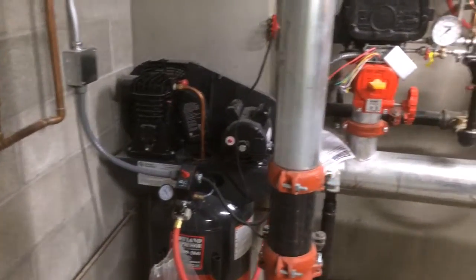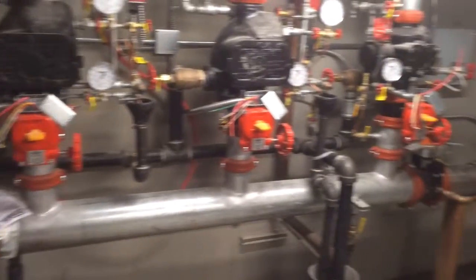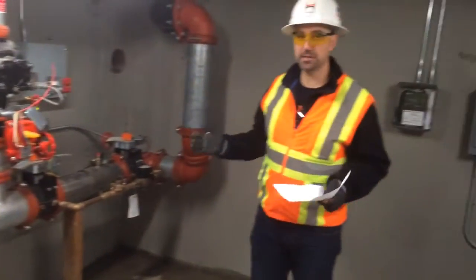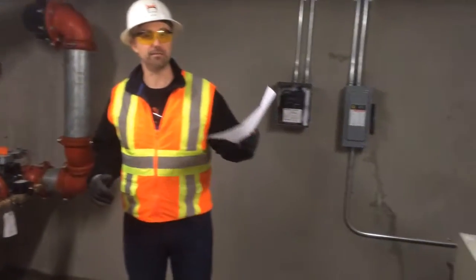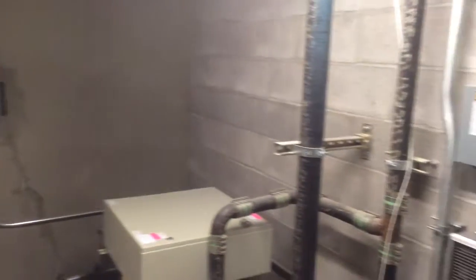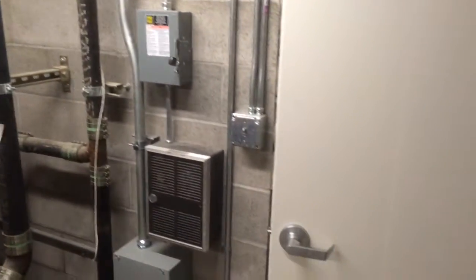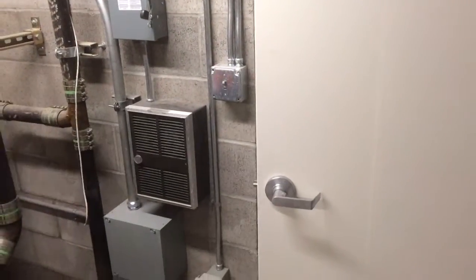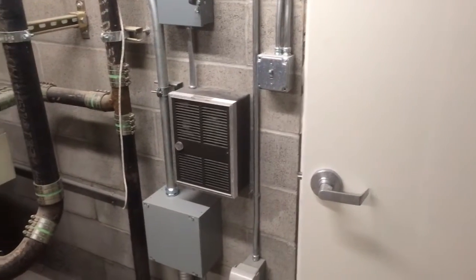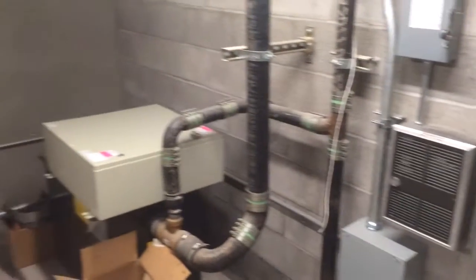As far as coordinating the architectural design, this space needs to have some attributes. The first one is it needs to have a locked door, it needs to have a sign on the door, and then it needs to be conditioned. We do that with a heater in this case, because we do have dry or wet piping and we don't want to flood it.